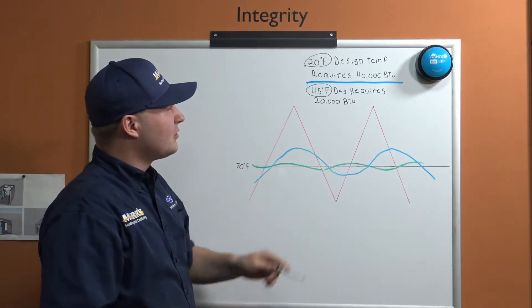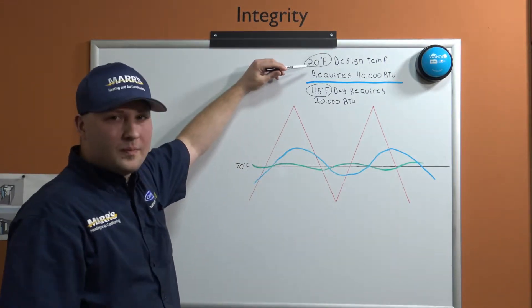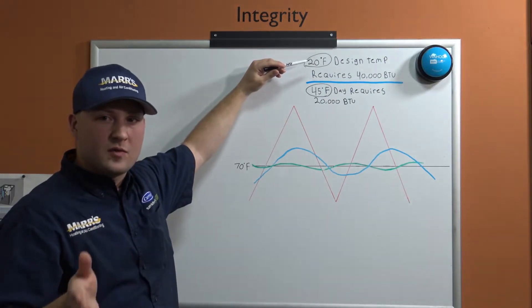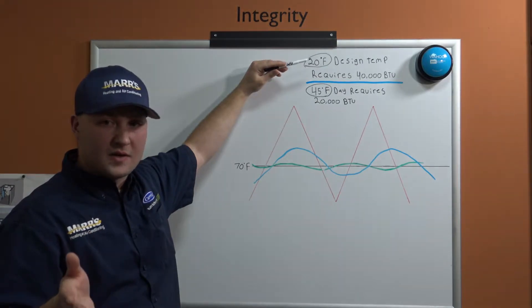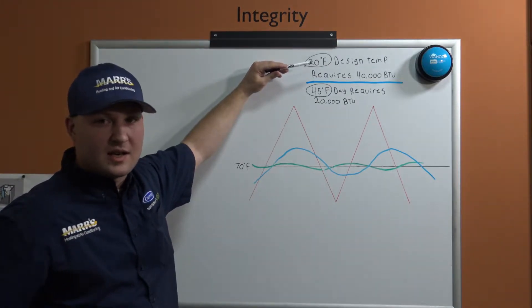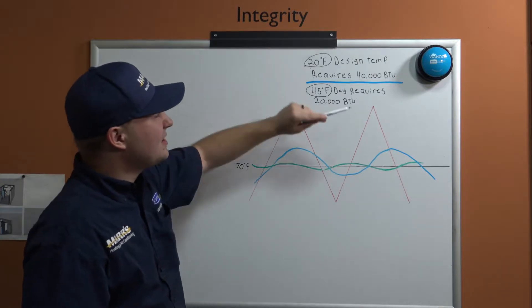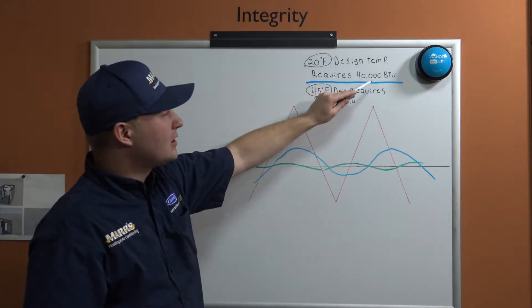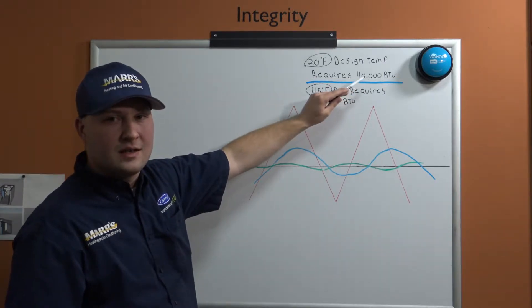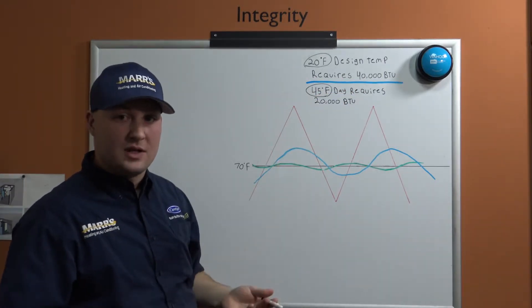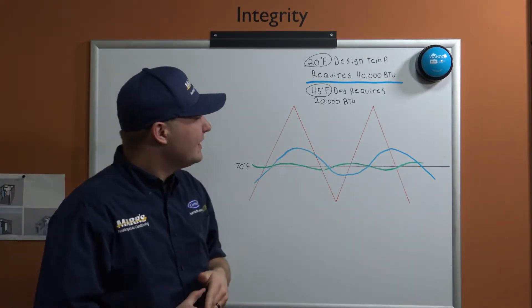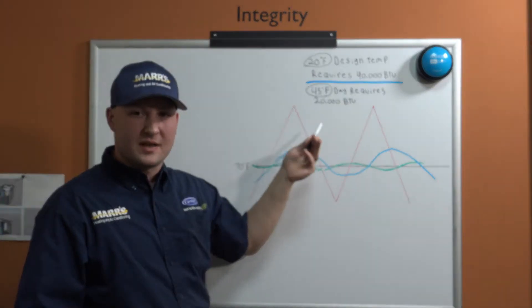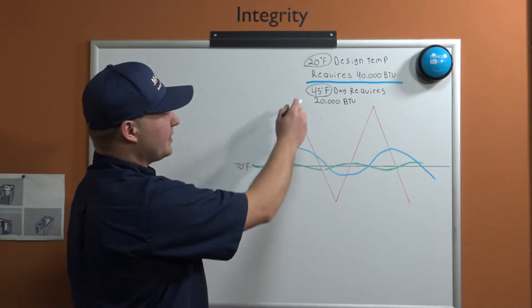At 20 degrees, your home—depending on insulation levels, the types of windows you have, how leaky the house is, how much air infiltration is getting in—let's say that this house at 20 degrees Fahrenheit requires 40,000 BTUs of heat to maintain 70 degrees indoor temperature. At 45 degrees that house only needs 20,000 BTUs to maintain 70 degrees.